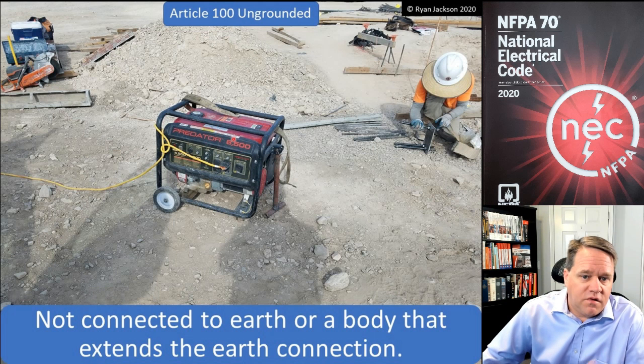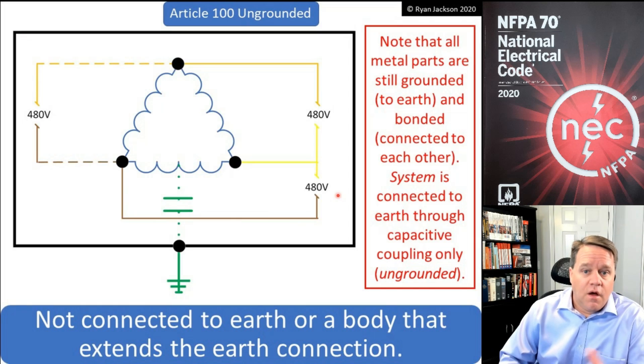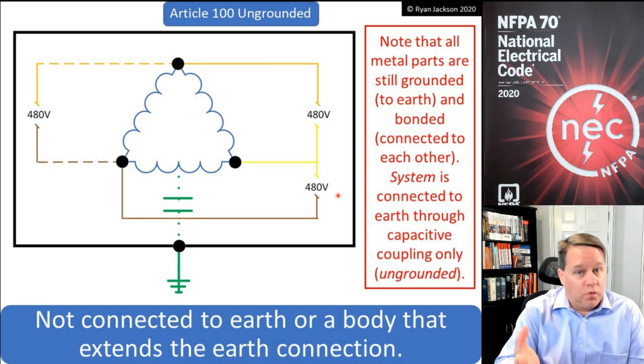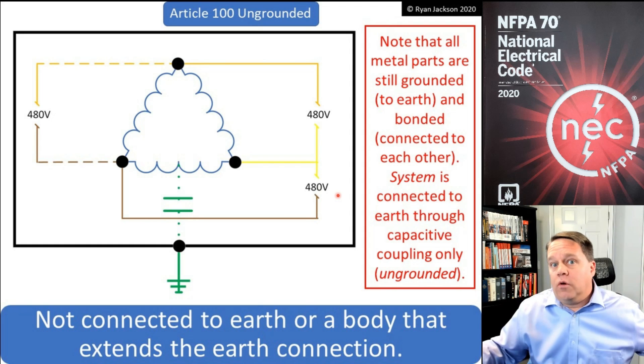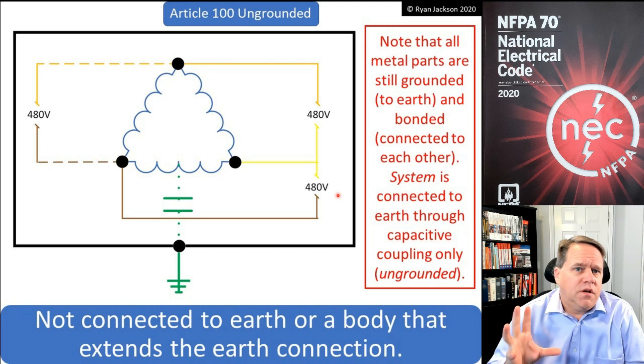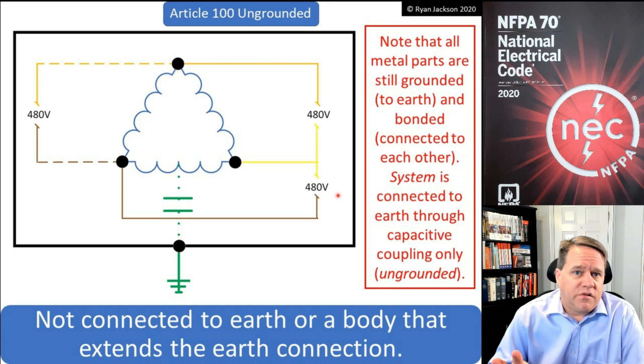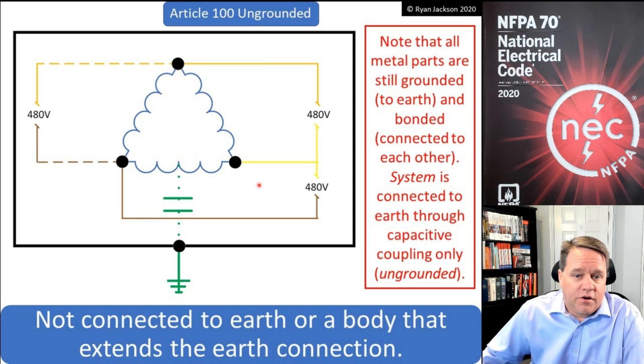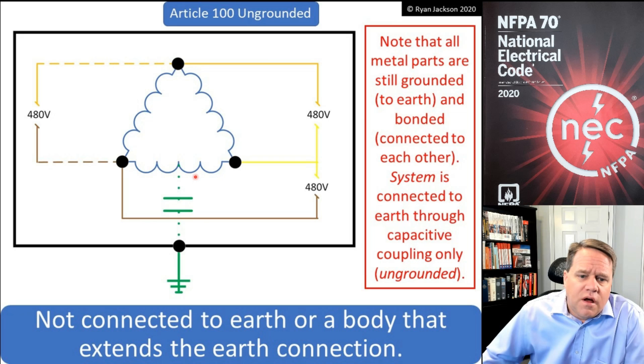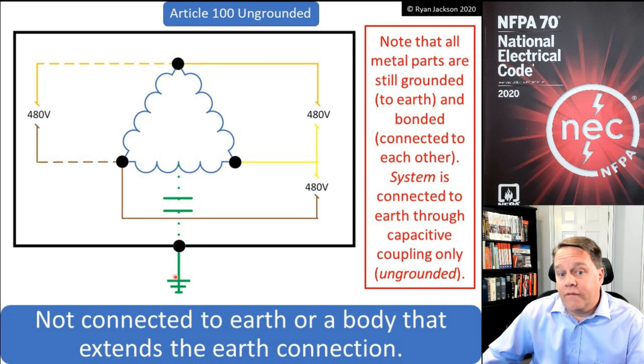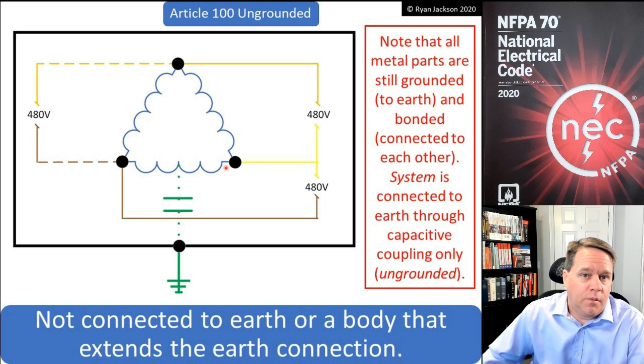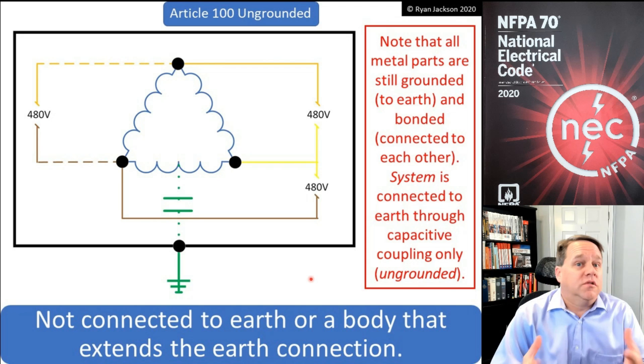This generator is an ungrounded system — the windings, the internal components, are not connected to the earth. For an ungrounded system, if we're talking about something bigger than a portable generator — an actual wiring system — you'd see an ungrounded system in some industrial facilities, usually older ones, though you can still install one today. An ungrounded system is usually a delta: a three-phase, three-wire delta, 480V. The metal parts and the transformer enclosure are grounded and connected to the earth via a grounding electrode system — maybe two ground rods or a concrete-encased electrode. But the actual windings of the transformer are not connected to the earth. That's an ungrounded system.